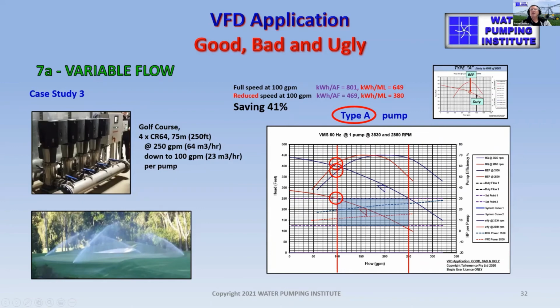So we start off running a pump efficiency of 68%, and we finish with a pump efficiency of about 66%. That's a pretty good balance, and everywhere in between there, the pump is running at a higher efficiency than that. So that's a big tick. That's an ideal size, ideal type of pump configuration to satisfy variable flows such as you would get on turf.